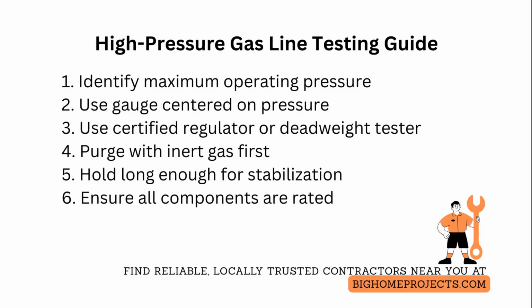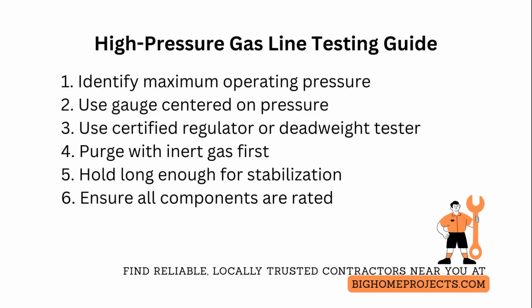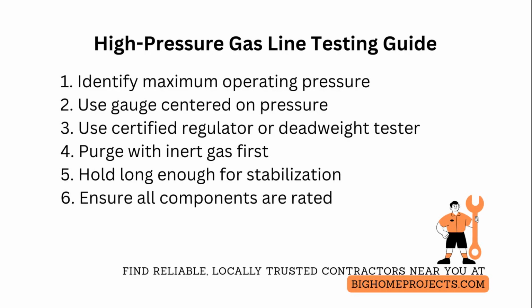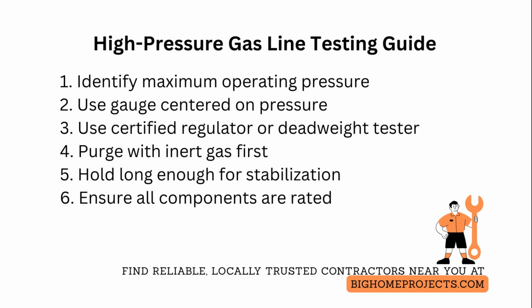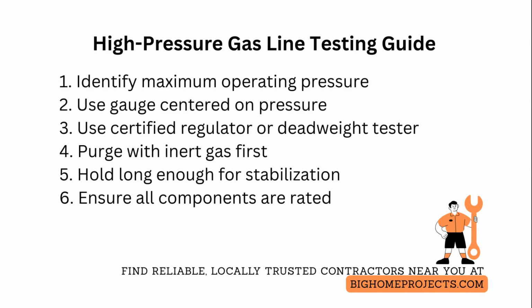Isolate the test section completely with verified blind flanges or capped fittings and purge the line of combustible gas with an inert gas like nitrogen before pressurizing. Never pressurize a system containing natural gas or liquefied petroleum gas during the leak test. Monitor pressure decay using timed, documented intervals and record ambient temperature because temperature shifts change pressure. If you see any drift beyond allowable decay, perform a soap bubble or electronic leak detection scan while holding the system at the test pressure.